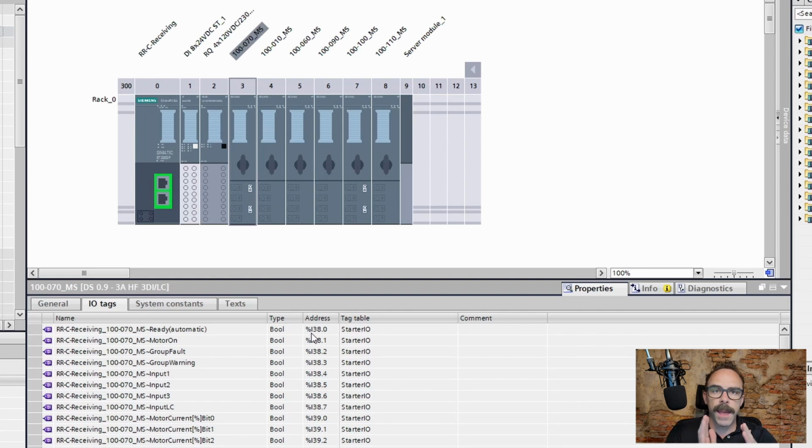The standard cyclic cycle time for a PLC, in the Siemens world, is determined by a block called OB1, so Organizational Block 1. Organizational Block 1 is basically everything that you want to just run as fast as it can, and that's kind of the main PLC loop. A lot of programmers, when they first start programming with Siemens, just put everything into OB1 and it works fine.